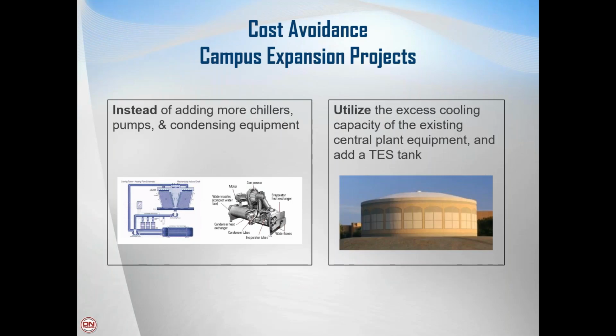And if the campus is going through an expansion, the owner has an opportunity to either add additional refrigeration equipment, cooling equipment, like a chiller and cooling tower, to provide that additional cooling for the campus, or perhaps they already have excess cooling capacity in their central plant at nighttime. And then instead of adding that refrigeration equipment, which you see on the left, they could add a tank, which you see on the right.